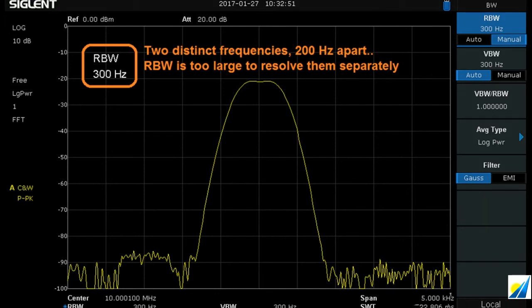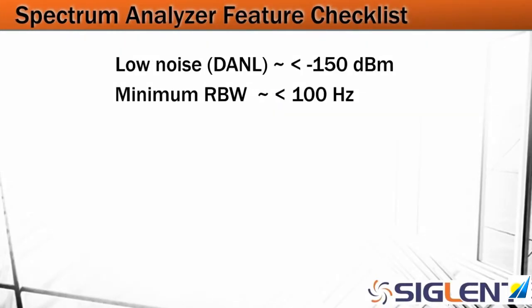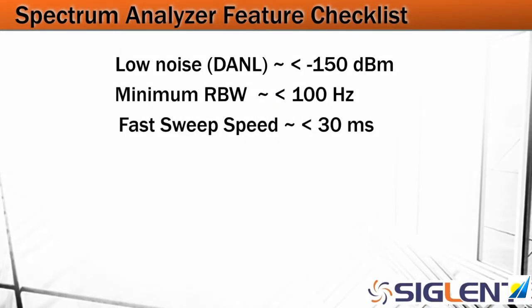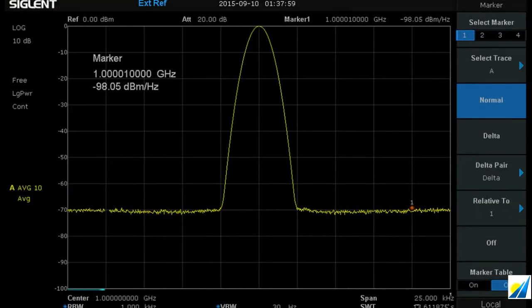Smaller resolution bandwidths are going to give you lower noise and more resolution between frequencies. We're also going to want a faster sweep speed — the faster the sweep speed, the faster we can collect data and get done with our job. You're also going to want to look for low phase noise; we want the phase noise of the measurement instrument to be considerably less than the phase noise of our device under test, especially when measuring transmitters and oscillators.